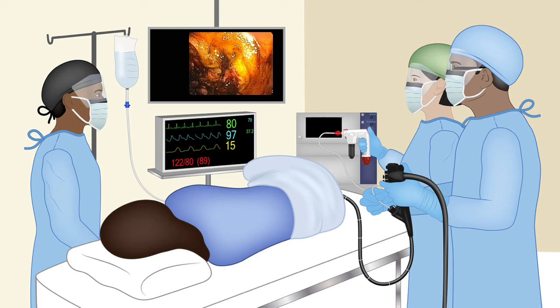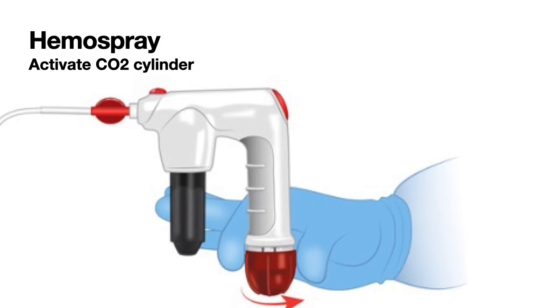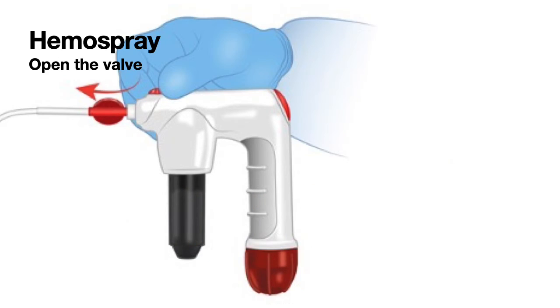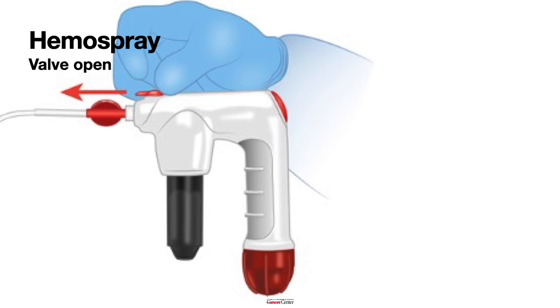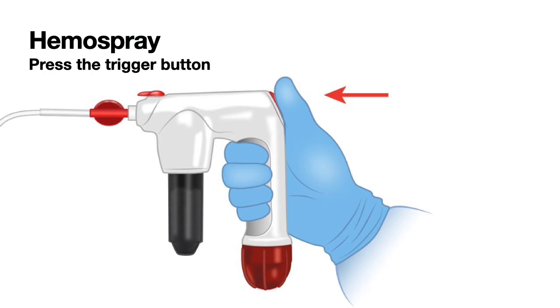So now you have the device ready, with the device attached to the catheter. The catheter is dry, and you want to start spraying. As part of the spraying, the next step is to activate the CO2 cylinder by turning the knob in the direction shown. All right. After activating the CO2 cylinder, you open the valve so that the gas can go into the catheter, and then press the trigger button to deliver CO2 along with the powder.